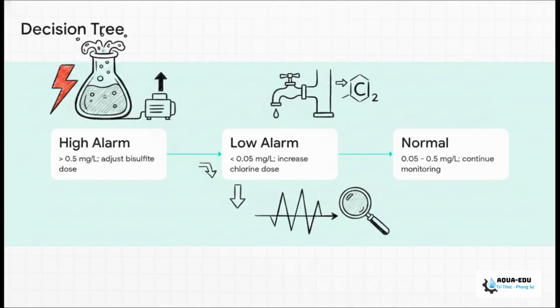Here is your operational decision tree moving forward. It's pretty straightforward. If your residual chlorine jumps over 0.5, your High alarm triggers. You must immediately check your bisulfite or SMBS dosing system and increase the dose to neutralize it. But if it drops below 0.05, your low alarm triggers, meaning you have to investigate your primary disinfection system upstream and likely increase the chlorine dose. Between 0.05 and 0.5, you just continue normal vigilant monitoring.